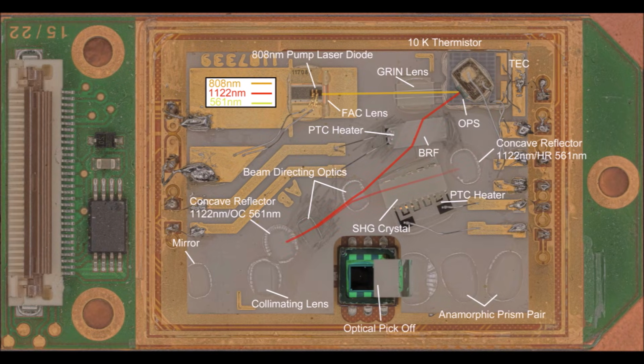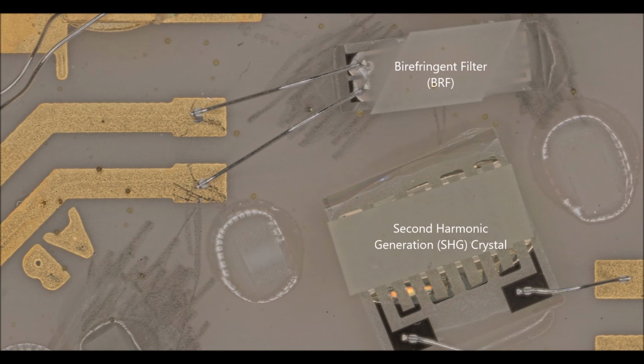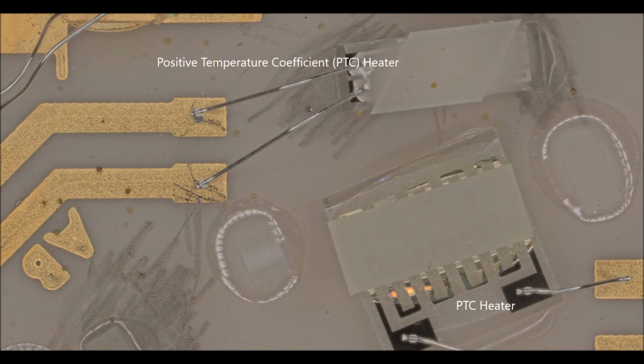1122 nanometer laser light then travels through the birefringent filter, which narrows down the bandwidth, ensuring only 1122 nanometer photons reach the second harmonic generation crystal. Both the birefringent filter and second harmonic generation crystal are on small positive temperature coefficient heaters.